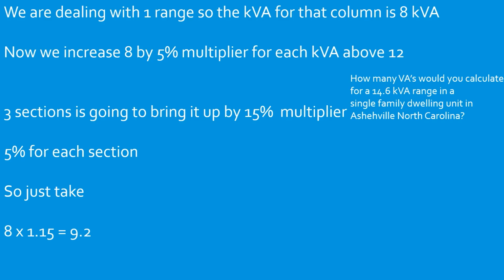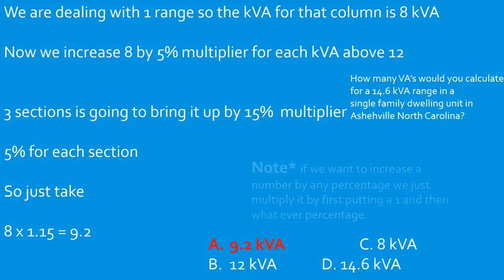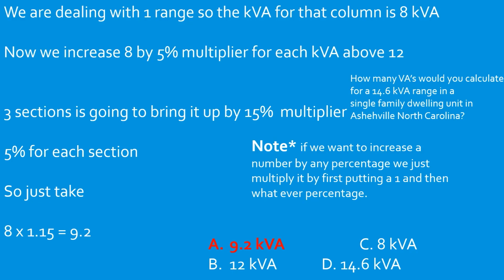us 9.2. Now I want to note that we are using 1 in front of the demand factor to increase it, okay? So we also could do 8 multiplied by 0.15 and then add it back to the original 8. But it's faster if you just do 8 multiplied by 1.15. That gives you your 8 back, and then it increases that 8 by 15%, and that's going to give us 9.2 kVA. So, super excited. You might have to go back through this one a couple times, but let's do another.